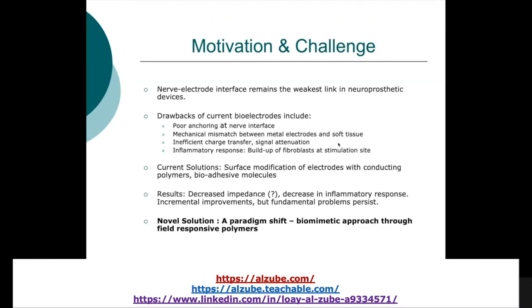That is one of the biggest challenges — why we would like to create a polymer-like electrode rather than a metal electrode. Current bioelectrodes have poor anchoring at the nerve interface. We would like to develop an electrode that can achieve attachment and adhesion to the nerve without damaging it. If anything touches a neuron, it immediately goes to controlled apoptosis or damage, which is a big problem. So we would like to generate an electrode that has adhesive properties without damaging the neurons.